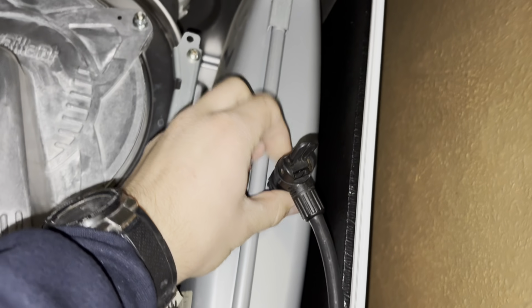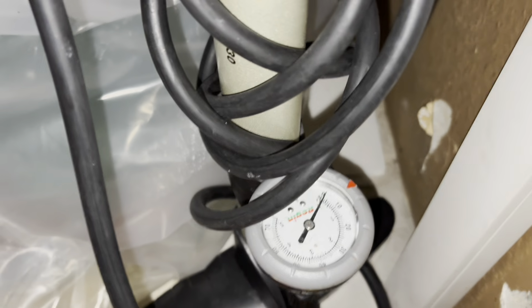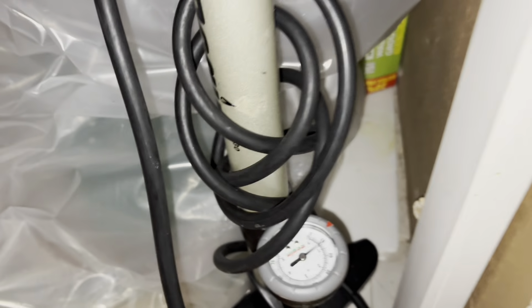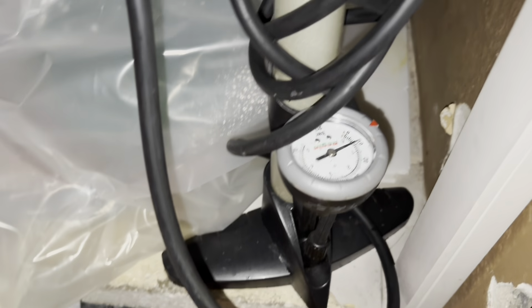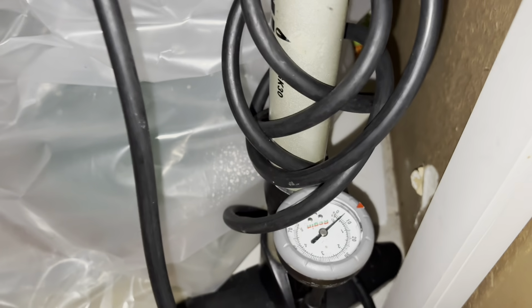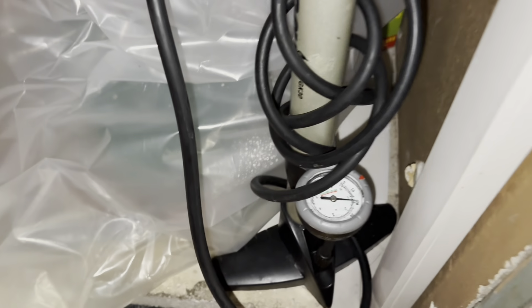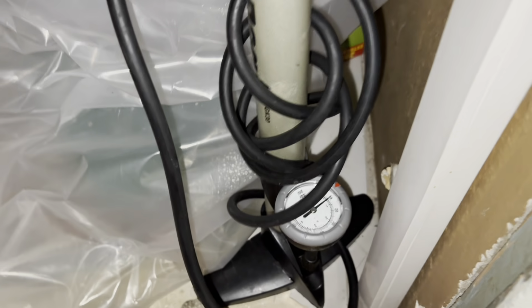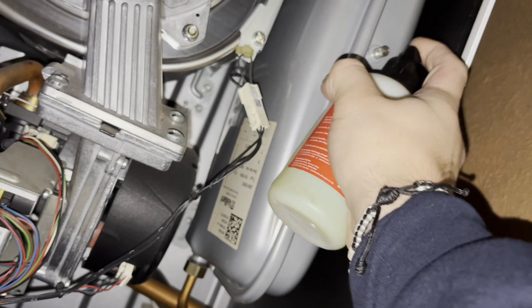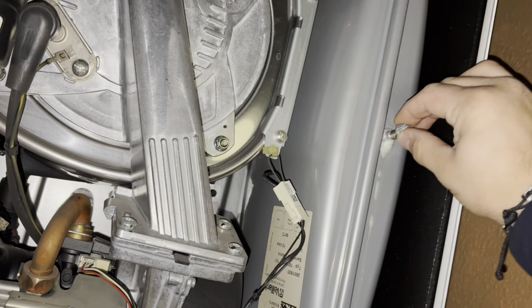As you've got the boiler drained down, you want to pump up the expansion vessel religiously when you drain down the boiler. As you can see, it's pretty much at 0. For a small flat like this, 0.75 should be fine. So just give it a little pump, pump, pump. One hand pumping. Right, 0.75. We're gonna remove that little LDF, make sure it's not leaking. No bubbles, no bubbles. It's all good. And that's fine. We'll close that up.